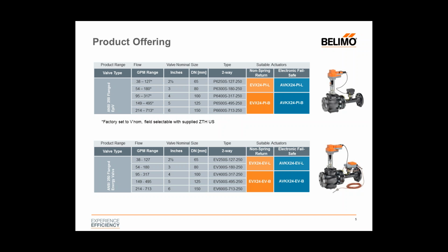It simply connects to the top of the actuator with a connector, a simple quarter turn click, and you can set not only the flow, but there are some other parameters like the control signal, just to name a few. It allows the customer to set the flow to whatever flow setting they want in the field. It's available in both non-spring and electronic fail-safe actuation. So that would cover the ePIV offering.